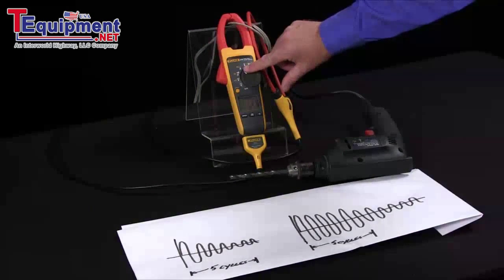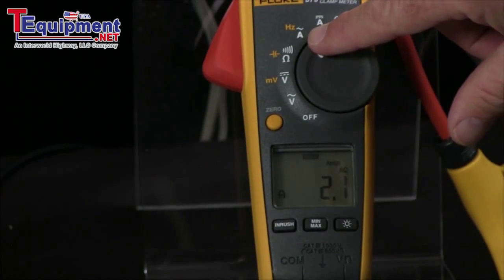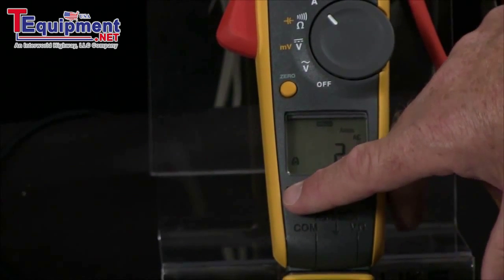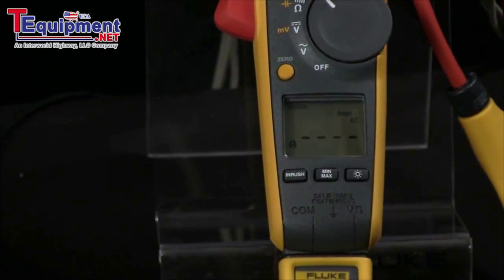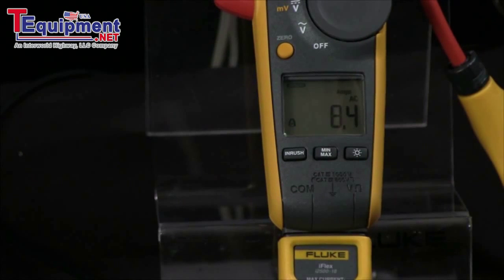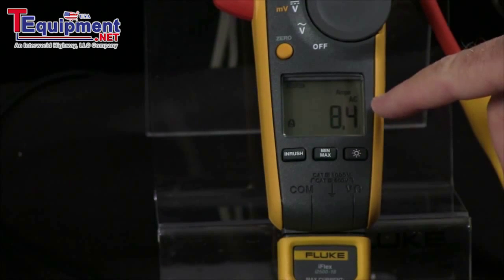we turn the clamp meter to the amp function and here we have the running current. To see what the starting or the inrush current is, I press inrush. The meter waits for the motor to start and then it captures my inrush so we can see that we have 8 amps versus the 2 amps.